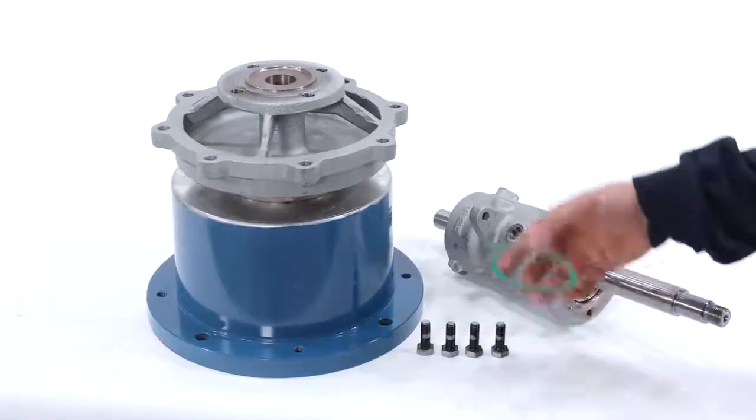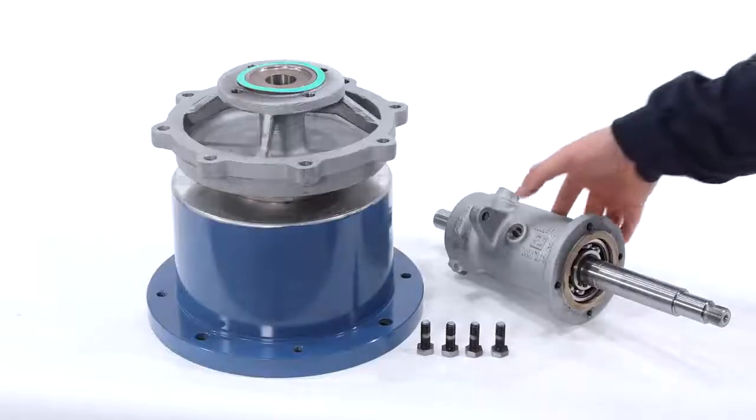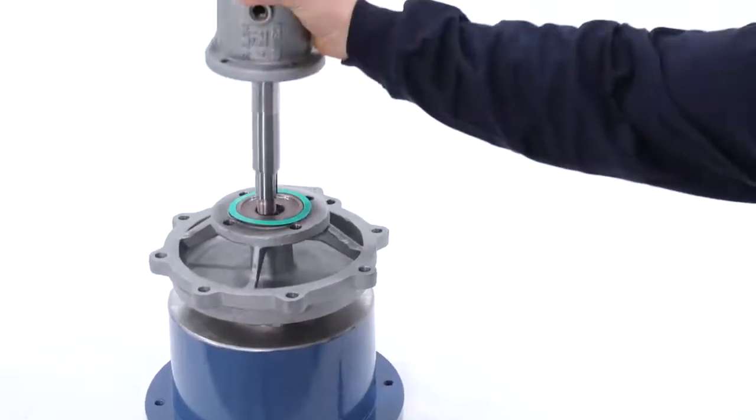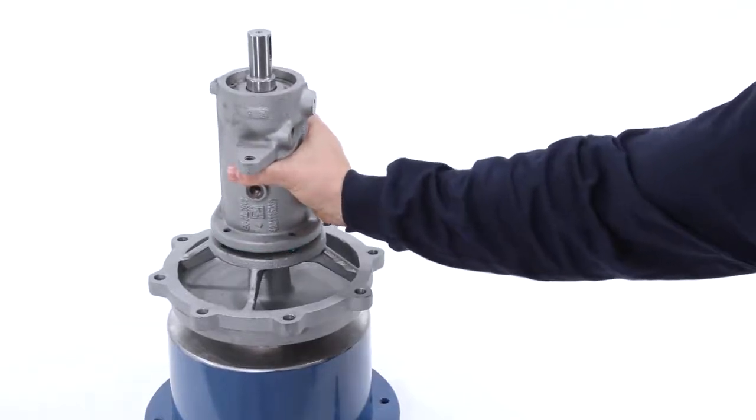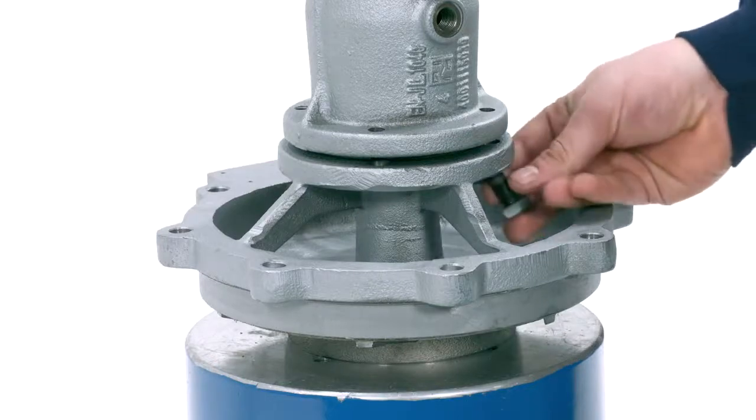Install the gasket. Mount the bearing frame into the casing cover. Install and tighten the four casing cover bolts with a 17mm wrench.